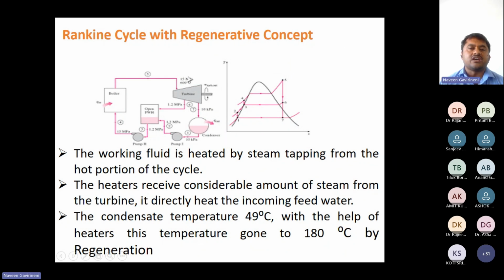But we are supplying 140 kg pressure here. What is the atmospheric pressure? 1 kg. So there is a chance of steam escaping from the turbine tip to the casing. For that purpose, we take the steam as bleed steam and supply it to the heaters. There are two types of heaters here, HP heaters and LP heaters. From the turbine's first stage we give to the LP heaters only. After that there is a deaerator arrangement for deaeration of the water, which I will explain in later slides.